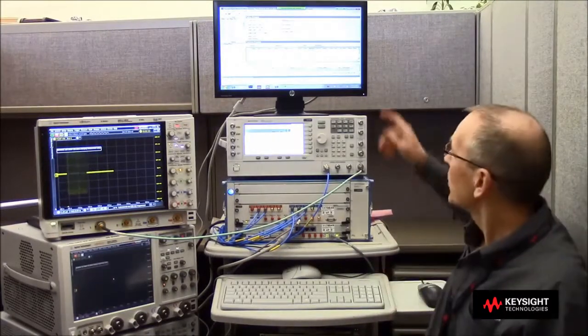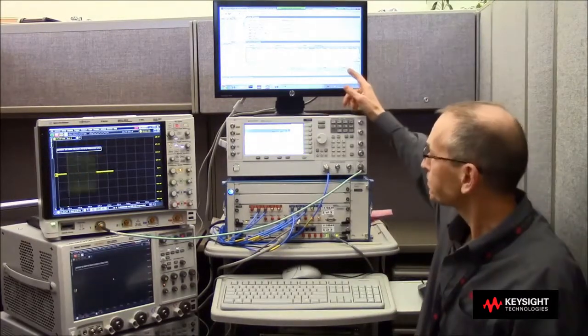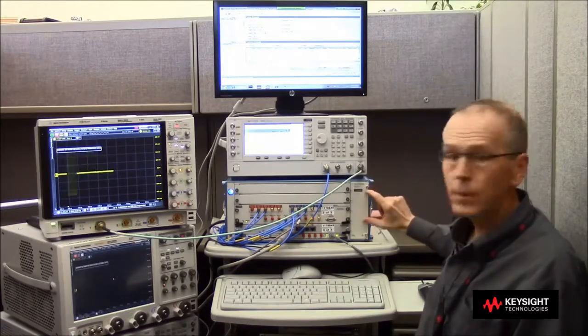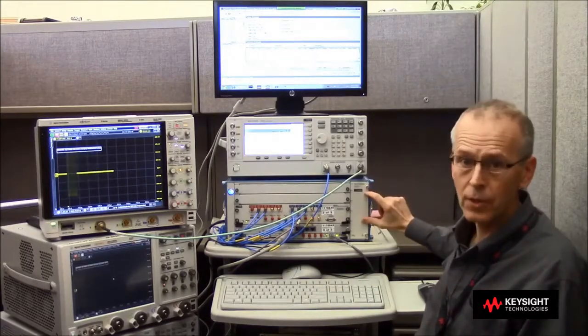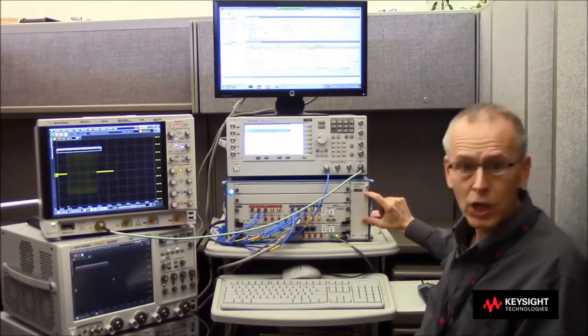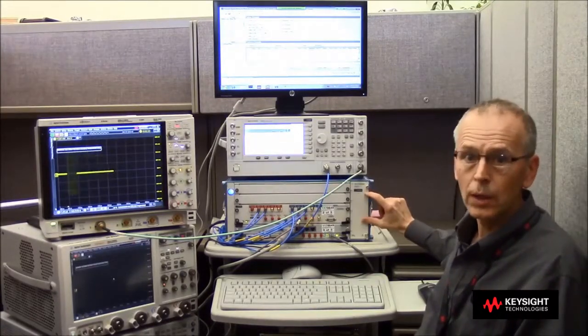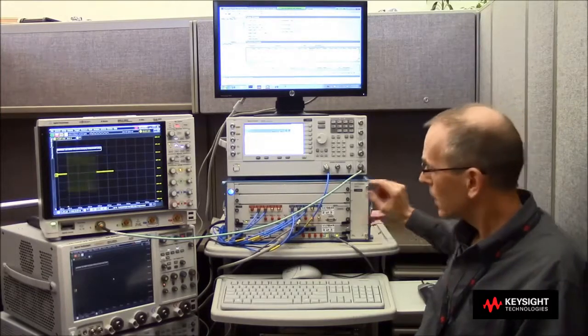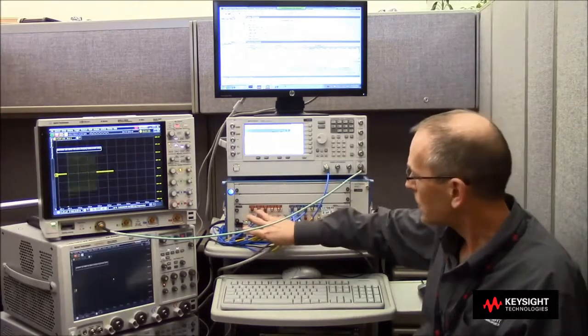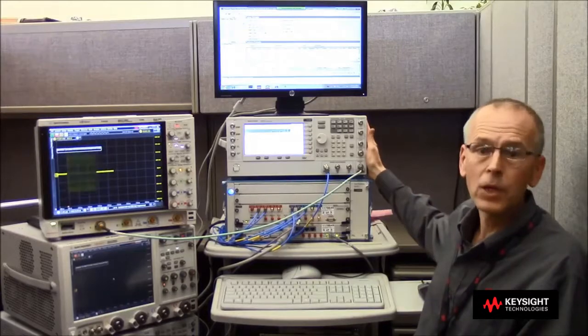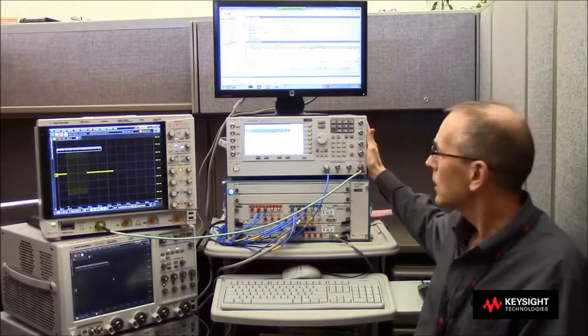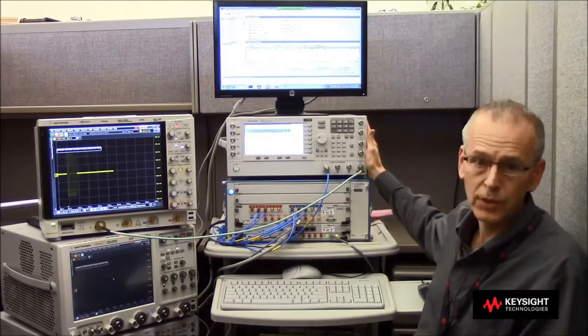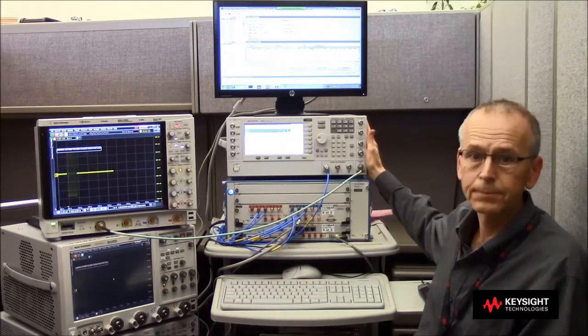The RF pulse signal is being created by Signal Studio Pulse Builder. That's driving an arbitrary waveform generator to put out IQ wideband modulation coming through cables into the wideband IQ inputs of a PSG signal generator.